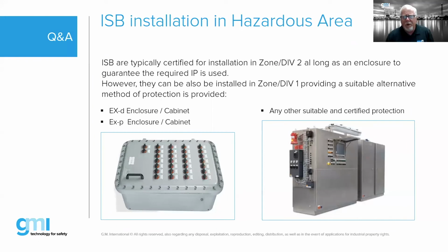So what you will find, most barriers are actually certified to be installed in either a Class 1 Division 2 or a Zone 2 area, and more or less in a non-flameproof type enclosure. There are some specific details, but basically they are certified to be installed in a Zone 2 environment in and of itself. However, if you need to install them in a Zone 1 environment, then typically you would have to take that barrier and install it in, say, for example, an EXD enclosure or an EXP cabinet. So just be aware of that.